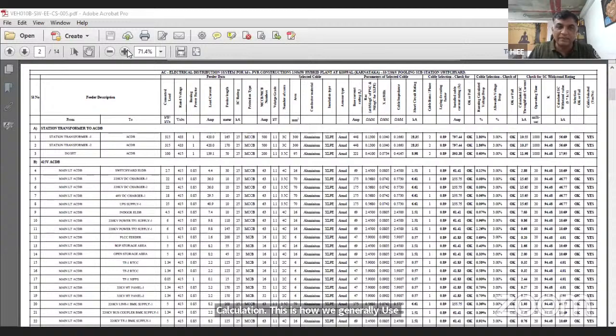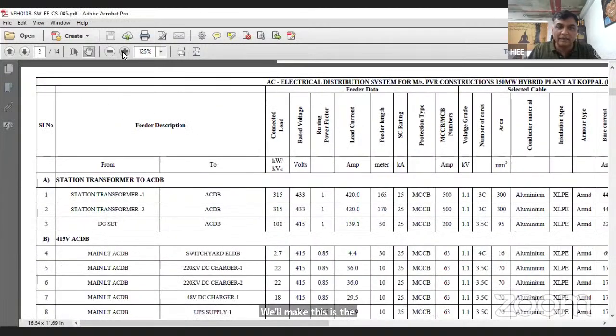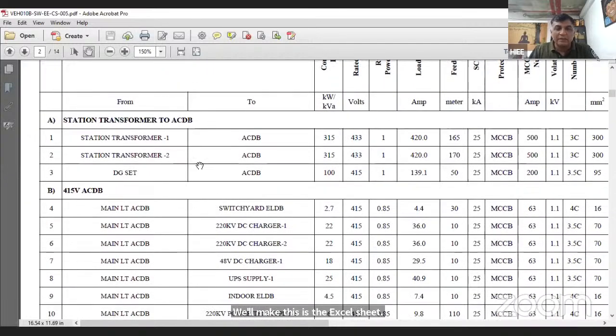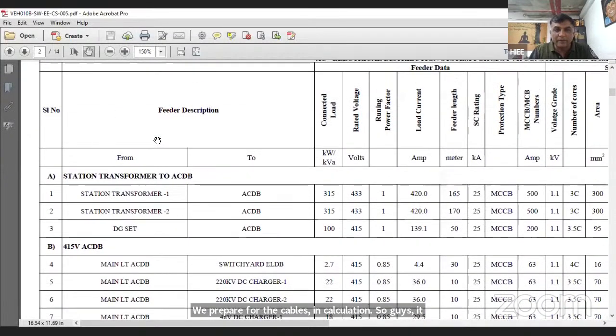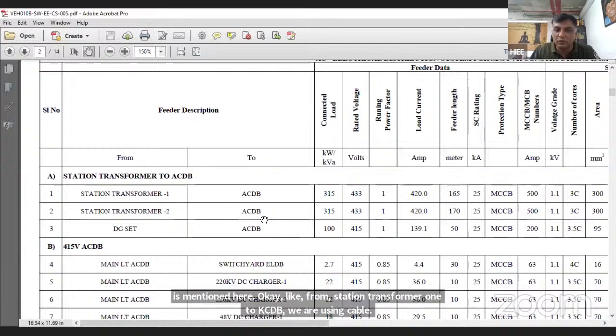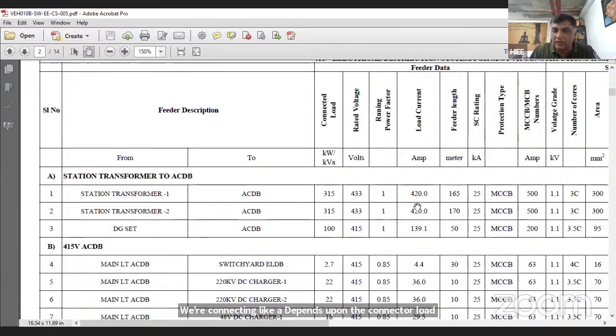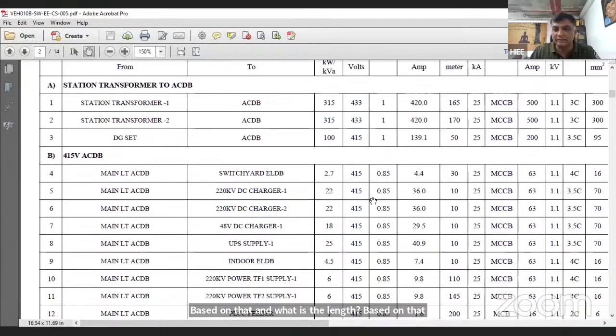This is the Excel sheet we prepared for the cable sizing calculation. So, guys, it is mentioned here. From station transformer 1 to ACDB, we are using cable. We are connecting station transformer 2 to ACDB, and DG set to ACDB. Depending upon the connected load, voltage, power factor, load current, and the length, we decide the cable size.